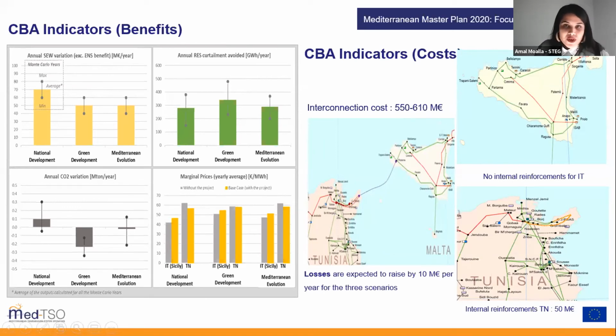For the network study analysis, eight points in time have been simulated. The N-1 static analysis applied at transmission level identified that there is no internal reinforcement needed on the Italian side, while on the Tunisian side we need a 400 kilovolt overhead line between Mornegia and Mlaba, and between Gromberia and Mlaba, as reinforcement. Those two lines will cost 50 million euro, and the interconnection cost will be between 550 and 610 million euros, depending on the converter station technology, LCC or VSC, and depending on the voltage level, 400 or 500 kilovolts.